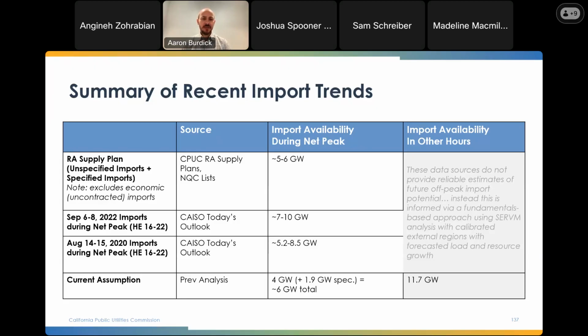The contracted imports we saw were roughly between 5 to 6 gigawatts of capacity, and the range for the heat wave events varied significantly depending on the hour, but roughly the minimum was about 5 gigawatts. Our current assumption in Resolve, when we combine the 4 gigawatts unspecified and the 1.9 roughly specified gigawatts of specified imports, gives us roughly 6 gigawatts total. So when we say 4 gigawatts of unspecified imports, the total imports includes the specified imports - we're really talking about 6 gigawatts of total imports.